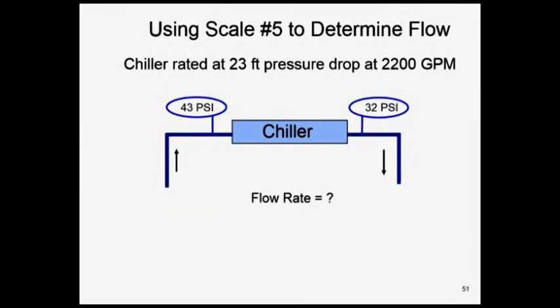If you make that reading with the same gauge, and the gauge reads out a little bit, you get rid of it because it gets subtracted. In this case, I would switch them and use both gauges, same side, for same readings, and hopefully I'll come up with an 11-pound drop with both sets of gauges. This is critical to you because a gauge can easily be reading a pound or two high or low. And when you move it and take a second reading, you get rid of that error and you get a much more accurate reading. Now, that out of the way, let's assume 11 pounds was accurate.